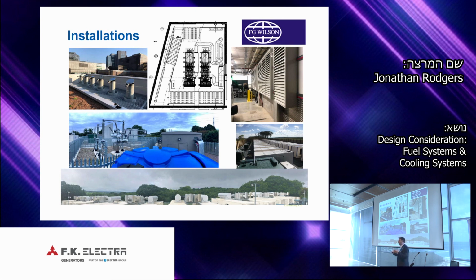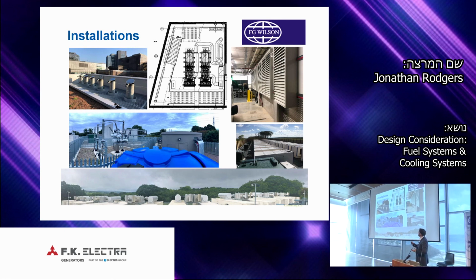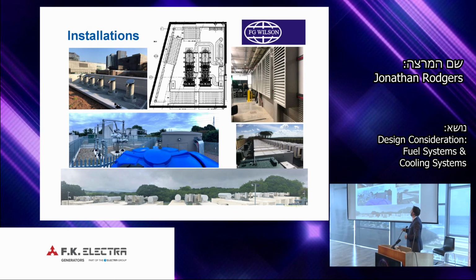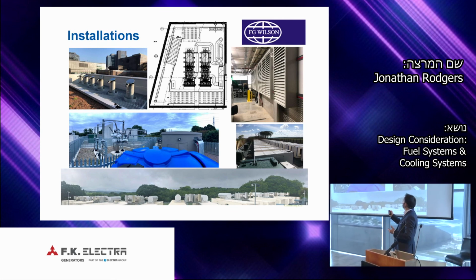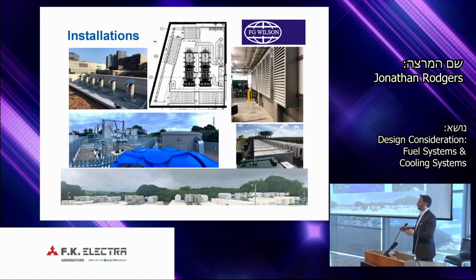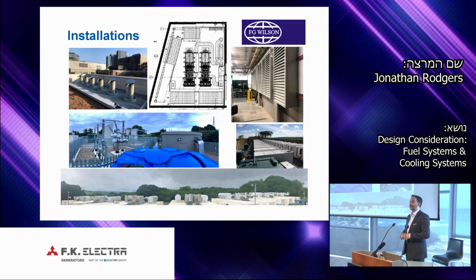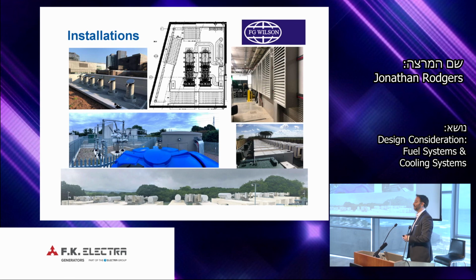Also, how the heat affects other equipment, neighboring equipment, whether it be switchgear enclosures or transformers. We have to direct where the direction of heat and the heat coming in, and what other elements are contributing to heat sources around the site. And then we have more complex installations where we're looking at how to get flow into a building, into a plant room. This may involve taking air into the side, a mix of direction of airflow. Some are where we have vertical discharge, where it's combined with exhaust discharges. We look at these as applications for application support, and we do a lot of very bespoke installations, but fundamental design parameters are still the same. We just have different change of pressure and flow.